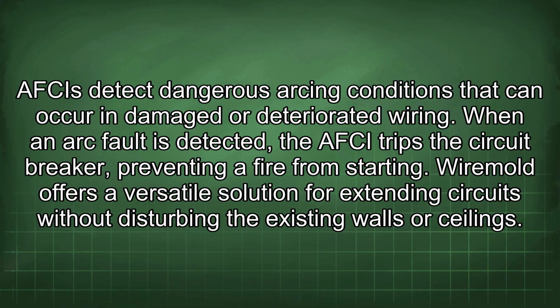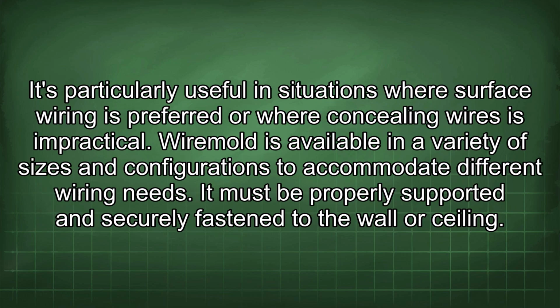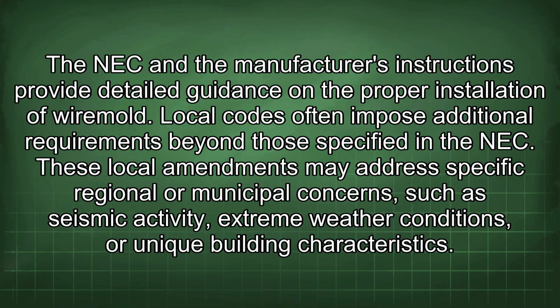Wiremold offers a versatile solution for extending circuits without disturbing the existing walls or ceilings. It's particularly useful in situations where surface wiring is preferred or where concealing wires is impractical. Wiremold is available in a variety of sizes and configurations to accommodate different wiring needs. It must be properly supported and securely fastened to the wall or ceiling. The NEC and the manufacturer's instructions provide detailed guidance on the proper installation of wiremold.